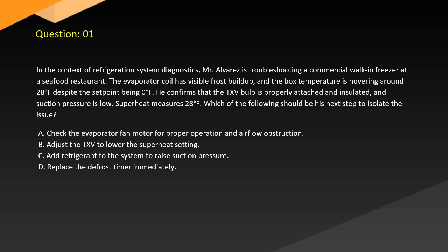Isolate the issue. A. Check the evaporator fan motor for proper operation and airflow obstruction. B. Adjust the TXV to lower the superheat setting. C. Add refrigerant to the system to raise suction pressure. D. Replace the defrost timer immediately.